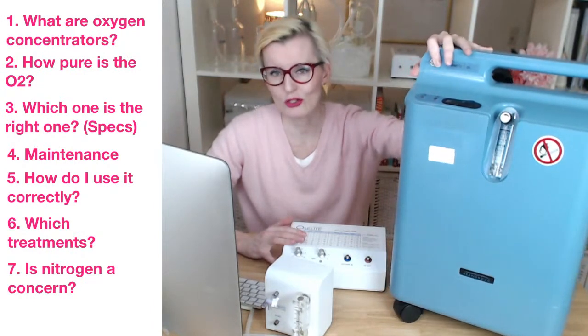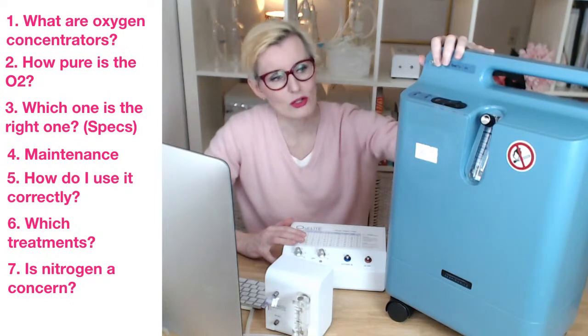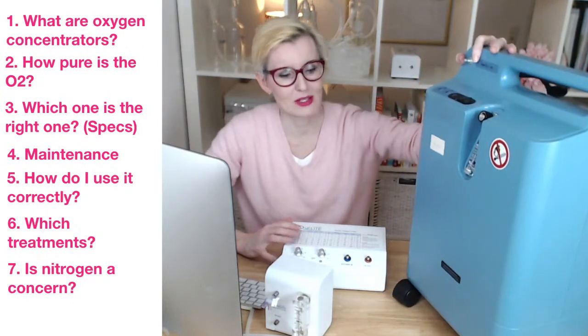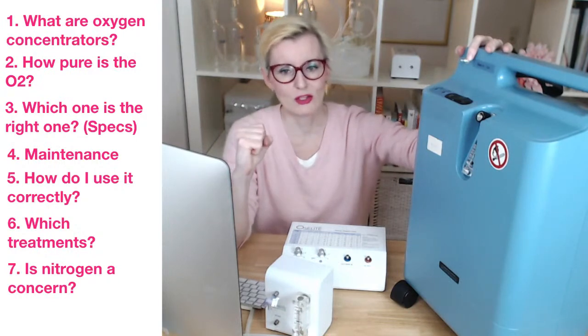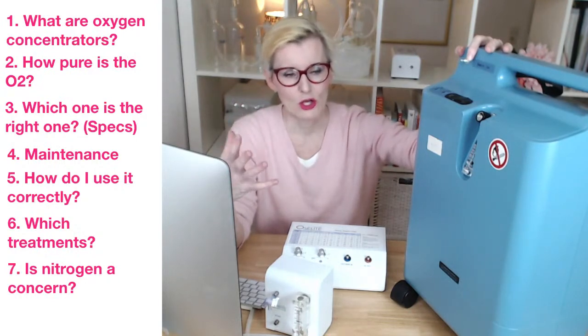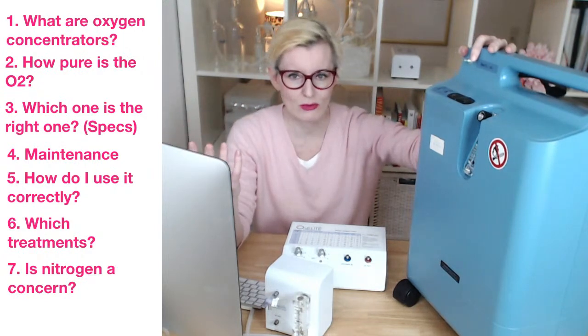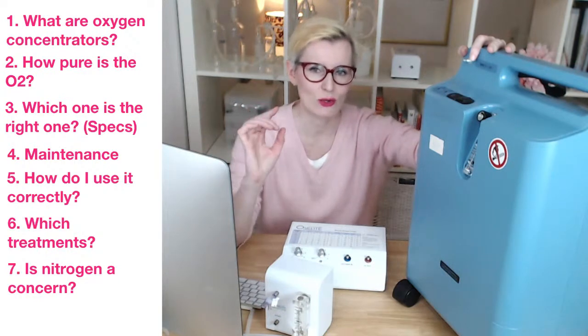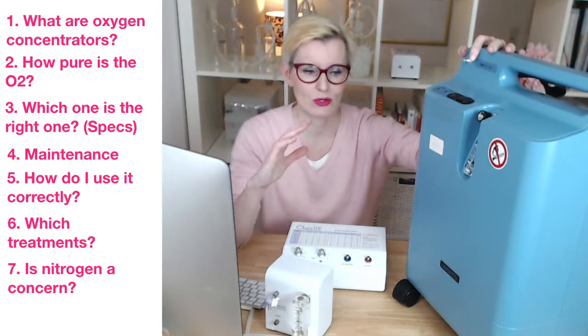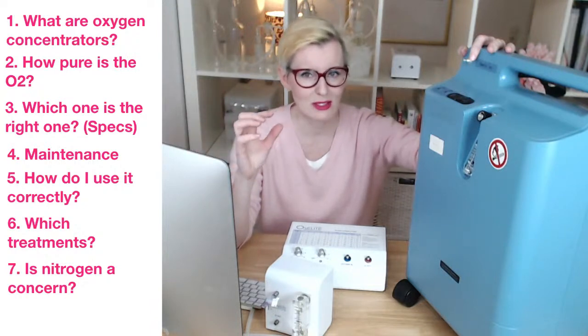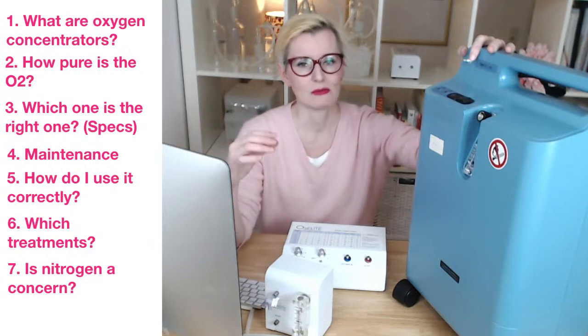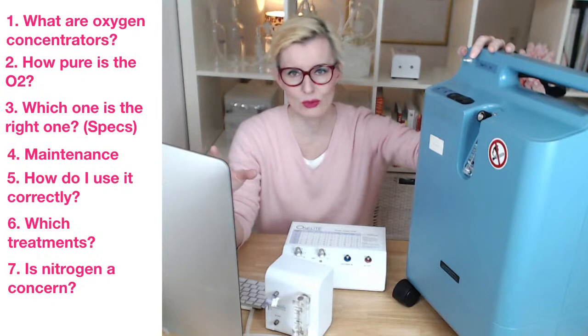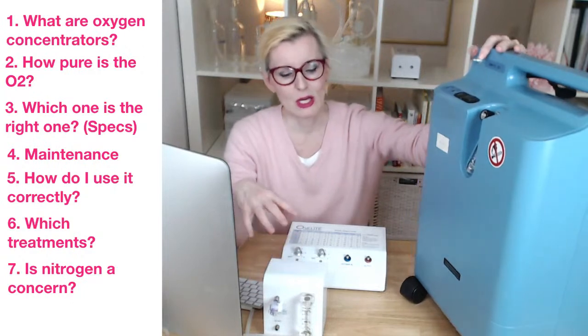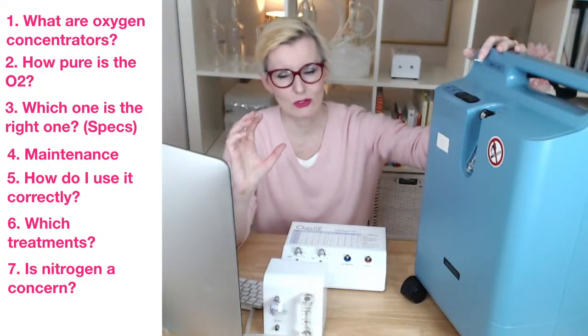Okay, so what are oxygen concentrators? How do they work? Oxygen concentrators work by concentrating the oxygen percentage, the oxygen content in the air. The air that we breathe, the air that is surrounding us, is made out of 80% nitrogen. So the overwhelming majority of what we breathe in is actually nitrogen, and only around 19 to 20% is oxygen. Then there are also gases like argon and CO2. CO2 makes up only 0.04% of the air that we breathe. So the air that we breathe in has only around 20% oxygen.